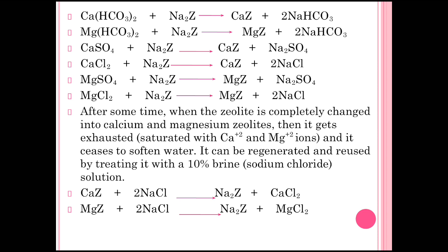When the capacity of exchanging ions with hardness salts is exhausted, it is called exhausted zeolite. Exhausted zeolite can be regenerated using a 10% brine solution (10% NaCl solution). When calcium zeolite reacts with sodium chloride, regeneration of sodium zeolite occurs.